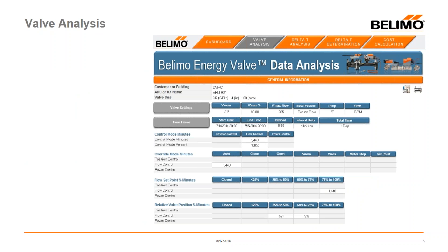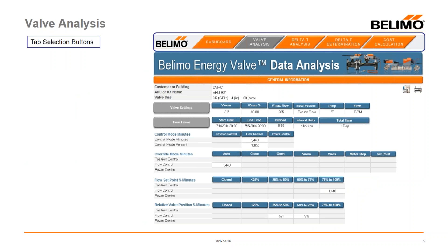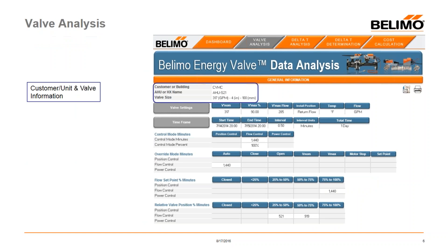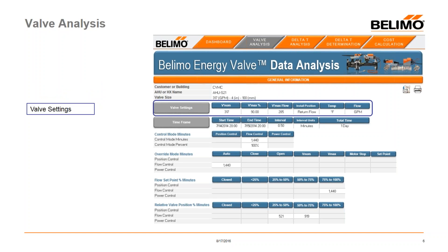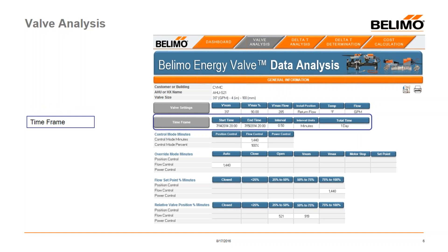The next tab is the Valve Analysis tab. Again, we start with the dashboard at the top of the screen for easy navigation between tabs. We display the customer name, air handler unit number, and flow rates for the valve so you know exactly what you're working with. We also display the valve settings — for example, a 317 gallon-per-minute valve set at 90% of its flow, giving a rated flow of 285 gallons per minute, installed on the return, with temperature in Fahrenheit and flow in GPM.